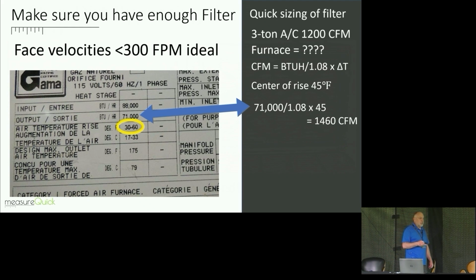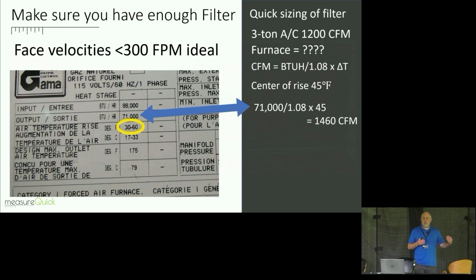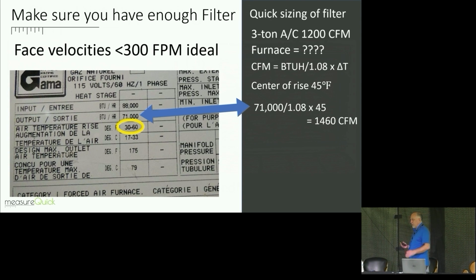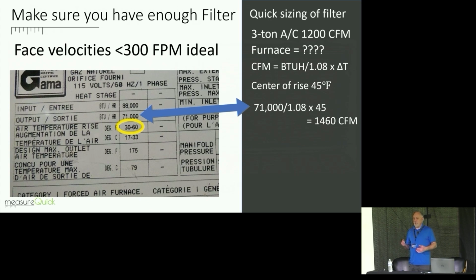Now, what have you guys noticed on a 90, like if you go to a 97% efficient furnace, what's one of the things that we've noticed now that's happening? What's happening to the temperature rise on the furnaces? It's going way down. Yeah, in fact, my old furnace on my house was a 60 to 100 degree rise, my 90 plus. My new one, I downsized it. I went from 100,000 down to a 75,000 BTU furnace. My new rise was 15 to 45 degrees. My new rise required more airflow, even though my furnace was downsized several sizes from my old one.